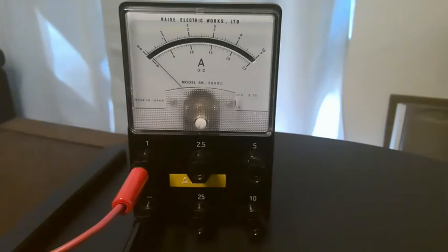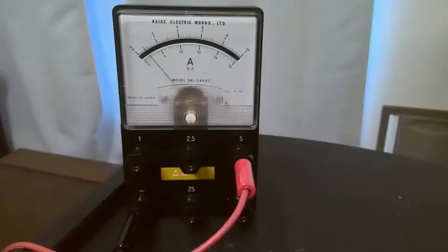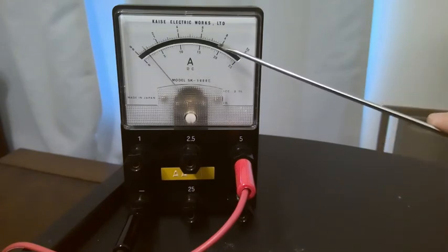Now let's look at how to use the ammeter to measure current. First, you should zero your ammeter. The method is the same as the voltmeter. The connection of the ammeter is very different from the voltmeter, but the principle of reading the ammeter is similar. First, you decide what range you're using, what scale you're using. And right now we are using 5 amps. That means we are using the second row of the labels, which reads 0, 1, 2, 3, 4, 5 amps.